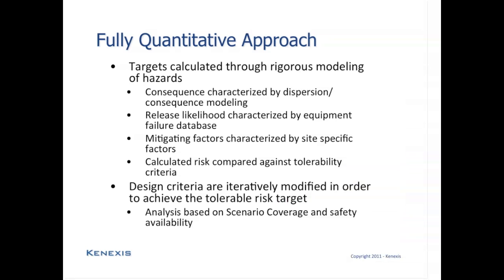Now, in order to fully understand the different approaches that are available for setting performance targets, it's best to start by understanding the fully quantitative approach. This is true not only for fire and gas system design, but safety instrumented system design and risk analysis in general. If you fully understand all of the attributes of a fully quantitative approach, it makes it easier to look at a semi-quantitative approach and understand what shortcuts have been taken, what simplifications have been made, and understand why those simplifications are appropriate and will still result in a risk calculation that will result in an effective design, even though the amount of effort expended on the risk analysis is orders of magnitude smaller.